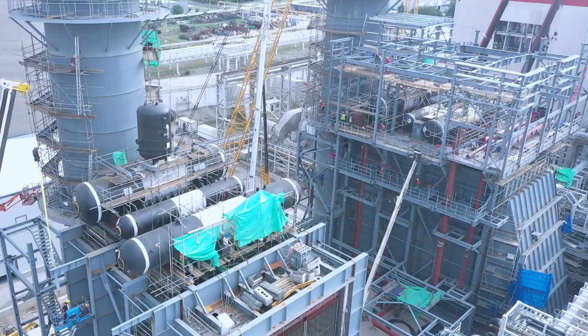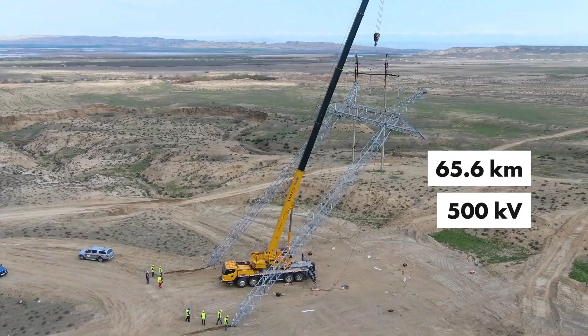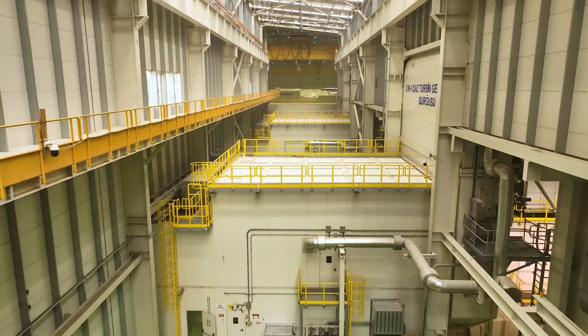To integrate the new power plant into the energy system, the 500 kV and 330 kV substations of the Azerbaijan TPP were completely reconstructed. Additionally, a 65.6 km long 500 kV Mingechevir-Samukh transmission line was built, and reconstruction works were carried out at the 500 kV Samukh substation. To increase the plant's overall efficiency, the steam turbines of Units 7 and 8 at the Azerbaijan TPP in Mingechevir were modernized by Azerenergy under guaranteed terms.